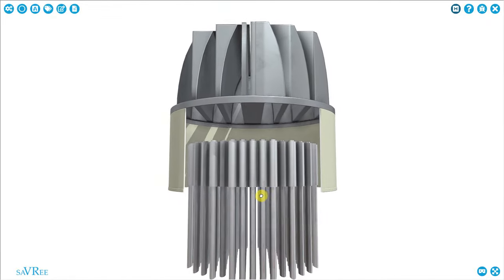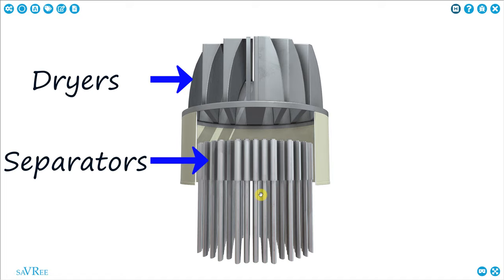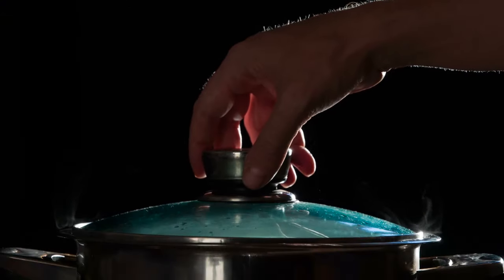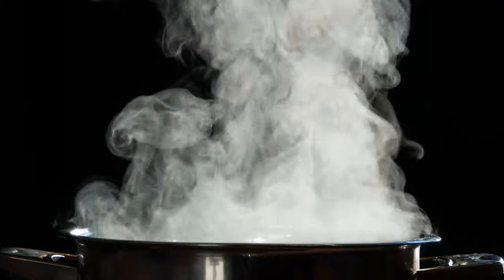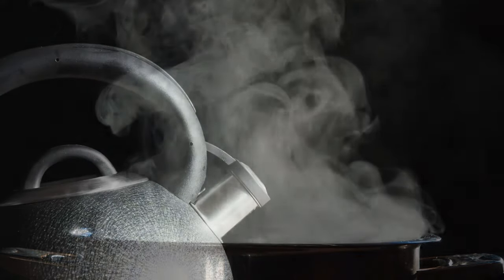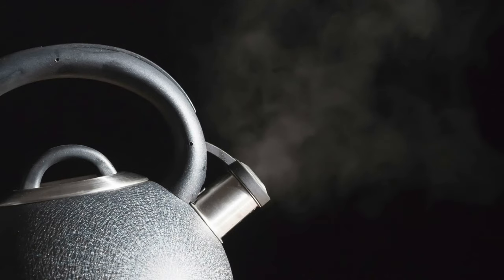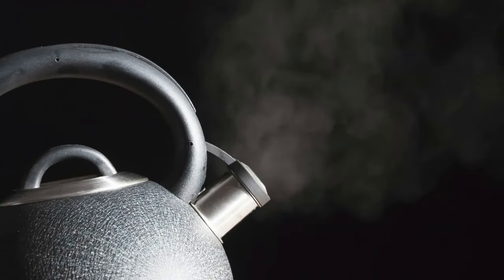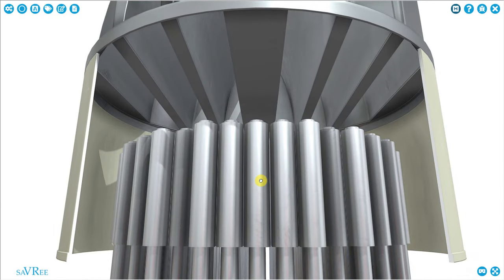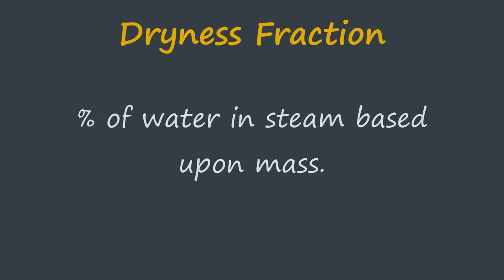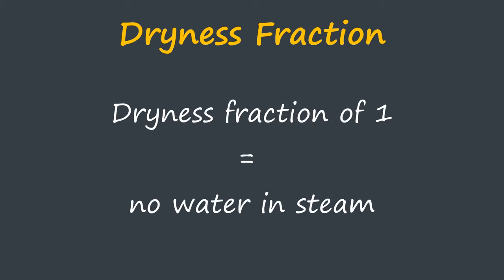So why do we have all this? We have this because the steam is quite wet. When you think of steam, you might think of it as having a white, fluffy, cloud-like appearance. You can't see steam in reality. Steam is a gas. What you're seeing when you see the steam come out of the kettle is actually moisture droplets, that's to say liquid water, suspended in the steam. If you remove these water droplets, then you will not see the steam. If you remove all the water droplets, then the steam is considered dry. If you have many suspended water droplets, then the steam is considered wet. We pass the steam up through the standpipes and the steam separators to separate out this moisture that's suspended in the steam. When we do that, the dryness fraction of the steam increases because it's drier than it was before. A dryness fraction of one indicates that the steam is dry. Less than that indicates that the steam is wet.